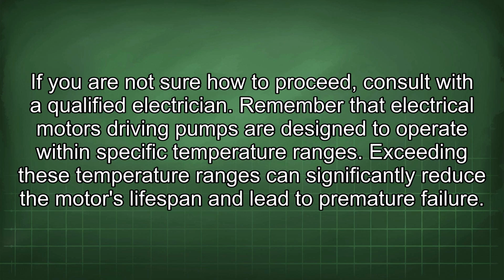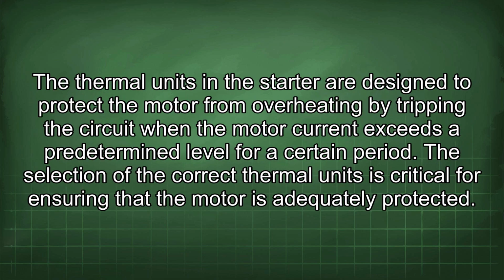Exceeding these temperature ranges can significantly reduce the motor's lifespan and lead to premature failure. The thermal units in the starter are designed to protect the motor from overheating by tripping the circuit when the motor current exceeds a predetermined level for a certain period. The selection of the correct thermal units is critical for ensuring that the motor is adequately protected.